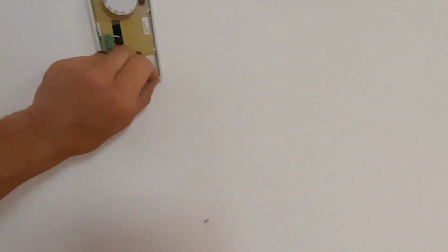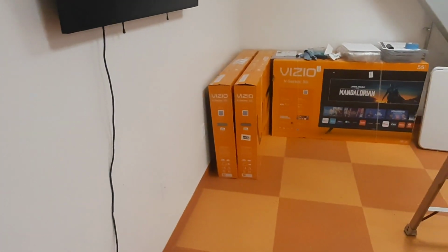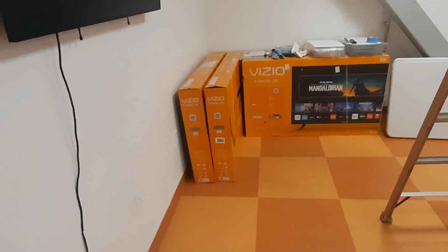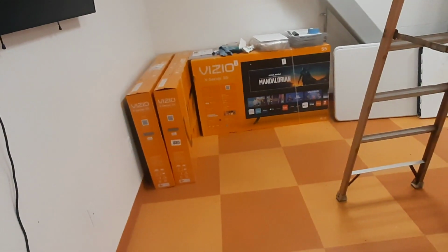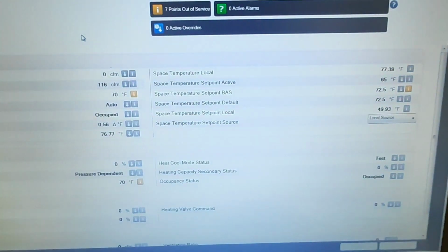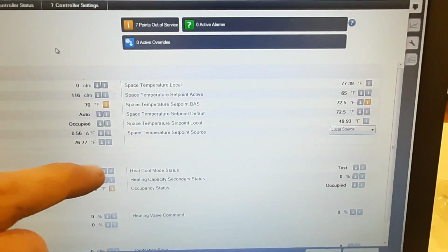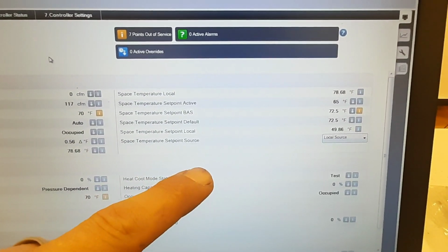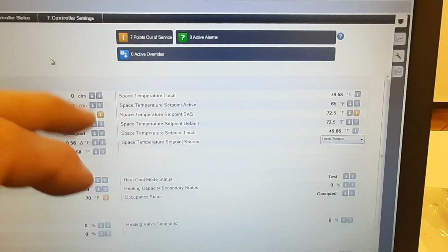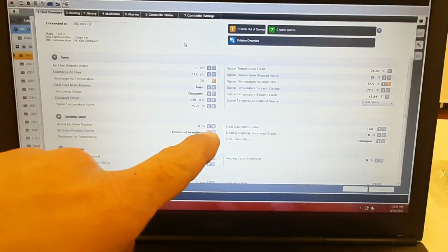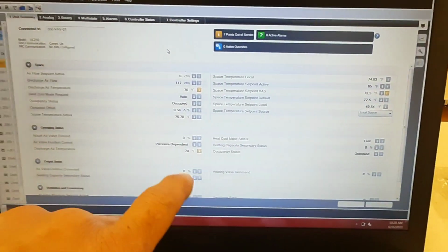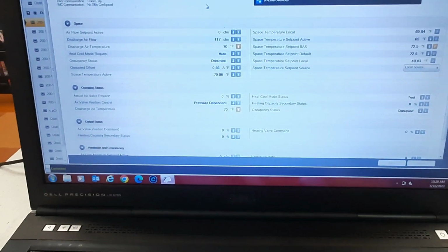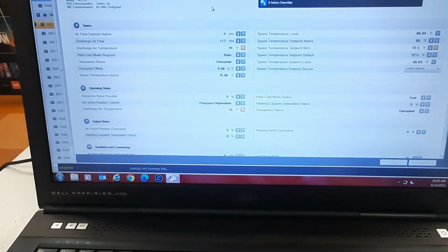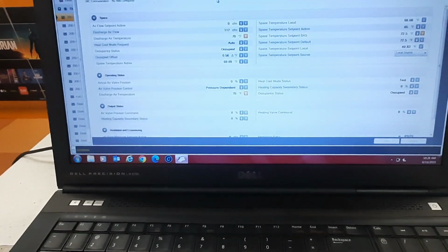I'll trick it and make it think it's warmer than it is. Let's warm that sensor up and see if that actuator drives open. So we warm the sensor up. Set point active, local set point 50, set point active is 65 because that's my minimum set point. It's cooling back down pretty quick, but I wanted to see my air valve open and close normally via the thermostat.